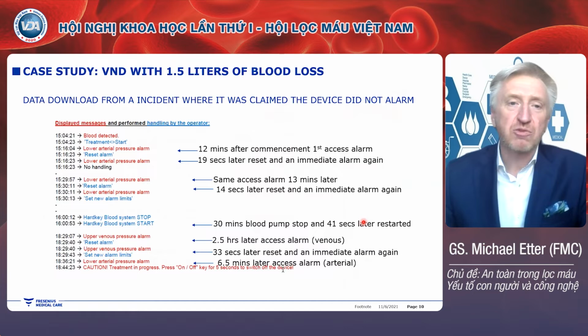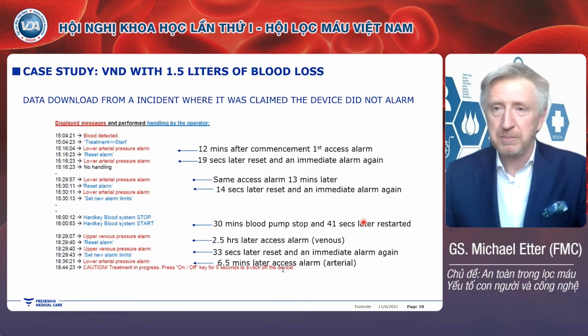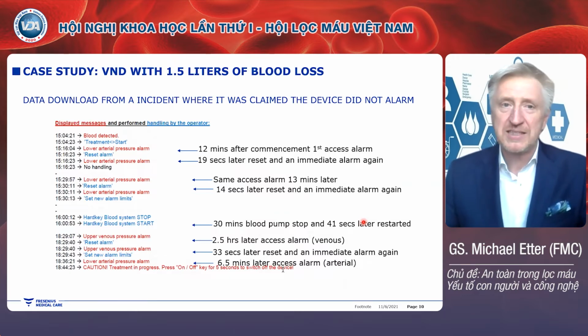You see here, all the reds are alarms, yeah? And at the beginning of the treatment, there were lots of alarms. And what is the natural reflex of many people in a dialysis unit when there is an alarm? The first thing is you quit, you reset the alarm, and you start the machine again.